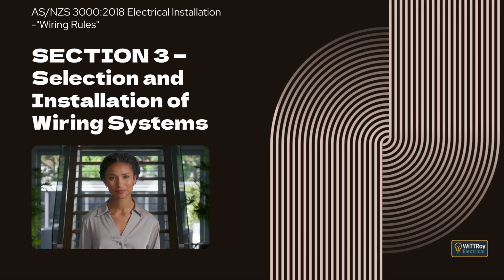Clause 3.11.4.3, Category B wiring system mechanical protection. This clause explains that Category B systems must be provided with additional mechanical protection. The protection must be placed no more than 75 mm above the cable, must be at least 150 mm wide, and must overlap the cable by at least 40 mm on each side. The protection may consist of materials such as concrete slabs, fibrous cement slabs, bricks designed for cable protection, polymeric cable cover strips, or other materials that provide an equivalent level of protection.